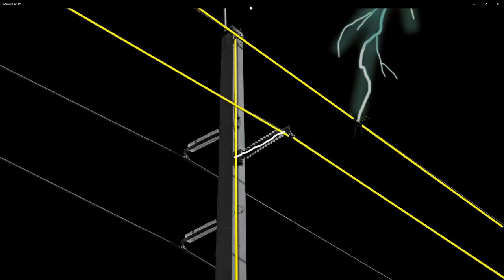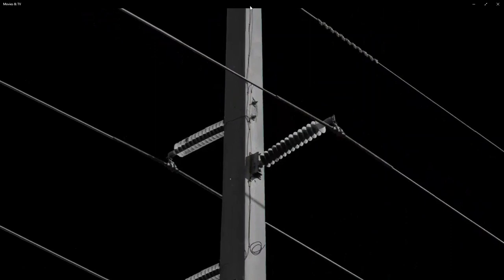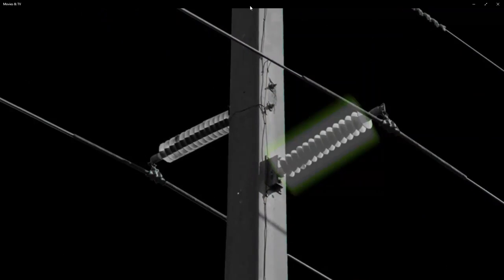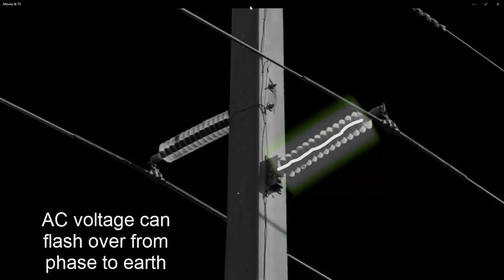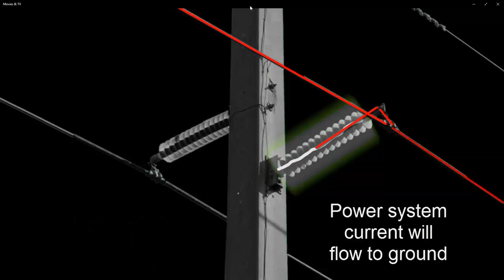When the stroke is over in about 100 microseconds, the ionized air along the insulator remains. This ionized air provides a perfect path for the normal AC voltage to then flash over from the phase to Earth. This second flashover is the issue.